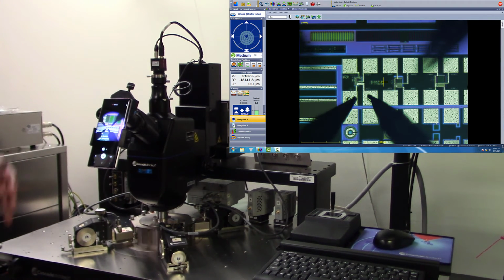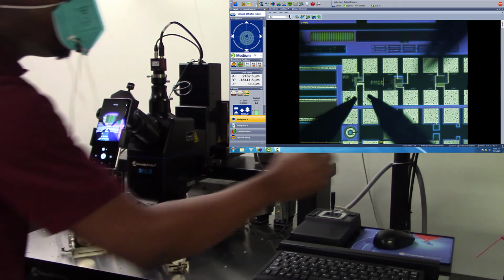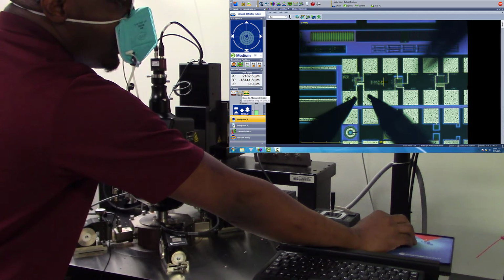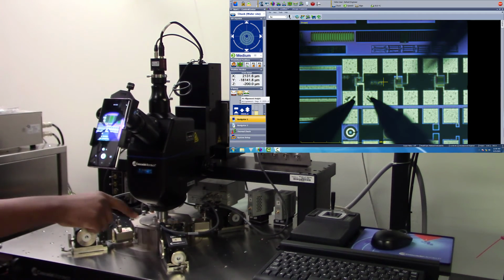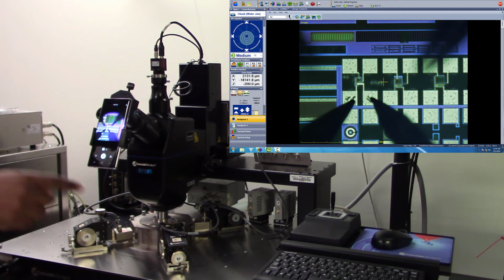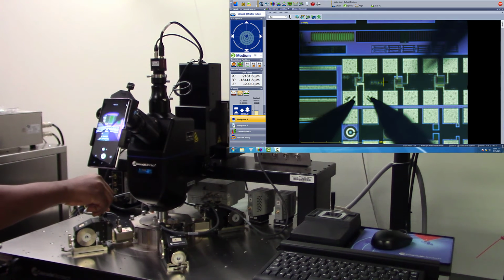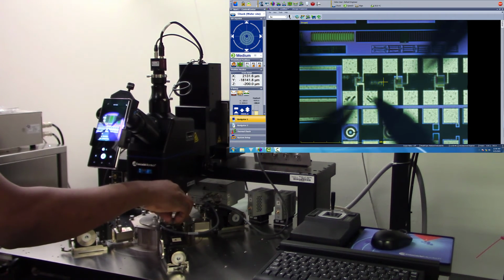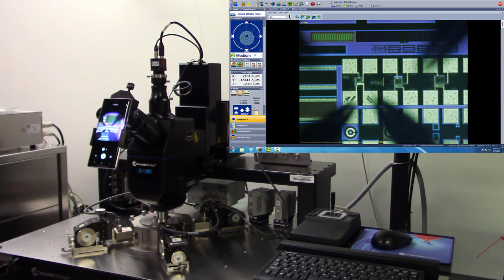After landing your probe tip and taking whatever measurements you need to take, all you need to do is go back into alignment height and rotate your Z position for your probe, for your micropositioners. You rotate them anti-clockwise for about 10 rotations. So I'm going to rotate this anti-clockwise for about 10 rotations. Rotating that anti-clockwise for about 10 rotations means that whoever is going to come in here and use the instrument is going to be at a safe distance between the probe tip and their sample, and they're not going to have the probe tip crashing onto the device.